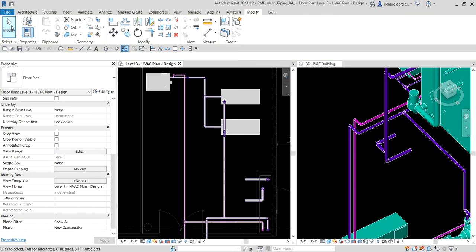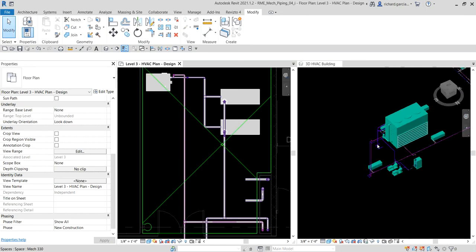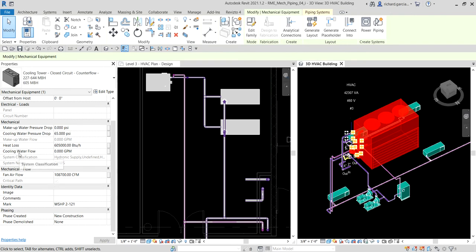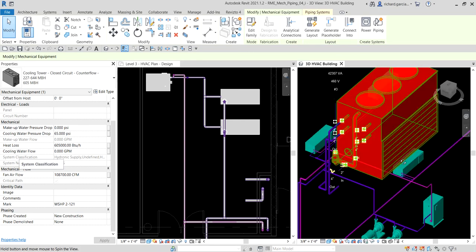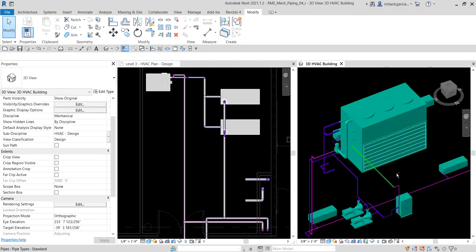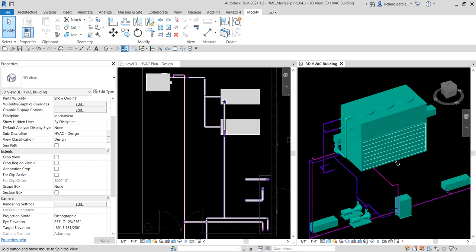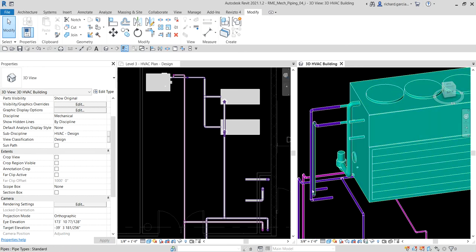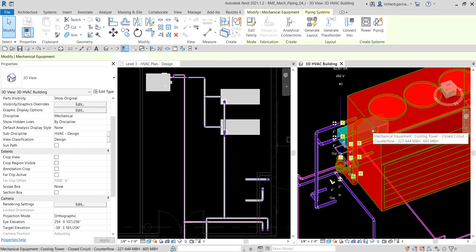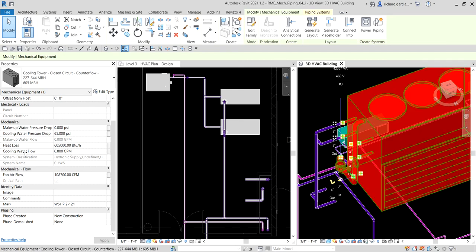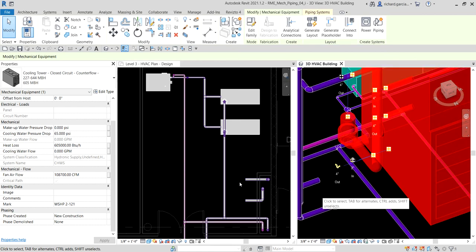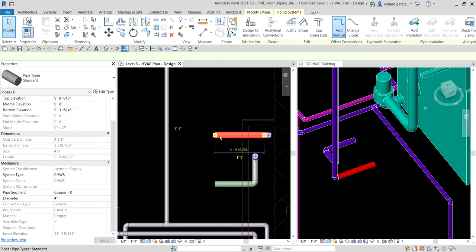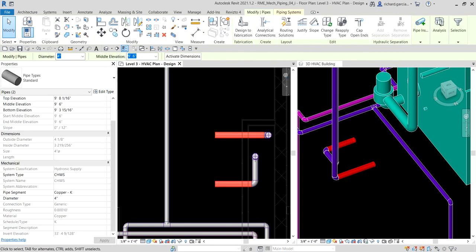Next we are going to connect the cooling tower. In the 3D view I select the cooling tower and check properties — the cooling water flow is zero, because the flow is not currently passing through the cooling tower. It is not yet connected to the hydronic piping system. We can see the cooling tower and the two pipes nearby that are not yet connected — that is why the cooling water flow reads zero.